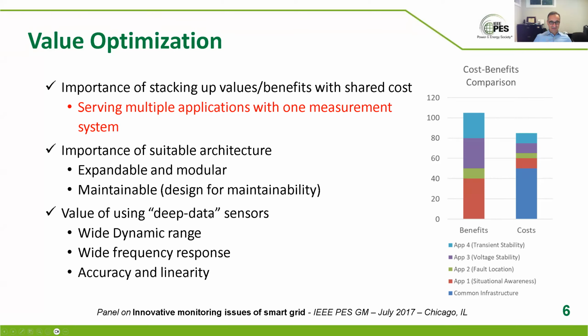Now, what I wanted to get to and refer to is the deep data sensor. These are sensors within the voltage and current measurement domain that have wide dynamic range, meaning they measure low currents and high currents, low voltage and high voltage, with similar accuracy. They have wide frequency response, so they're good for 60 hertz, but they're also good for harmonics and transients and other things, especially with renewables and inverters. You really want to see some of the higher frequency signals. And they have accuracy and linearity over this wide dynamic range and frequency. That makes for a deep data sensor, which, both in the dimension of linearity and the dimension of frequency, has a lot of capability and can really show what's in the high voltage and the low voltage. Each of these applications can use the data and filter everything else out if they want. They can use the data in the domain they're interested in. If it's a synchrophasor, it may filter only the 60 hertz. A different application could look at it differently.